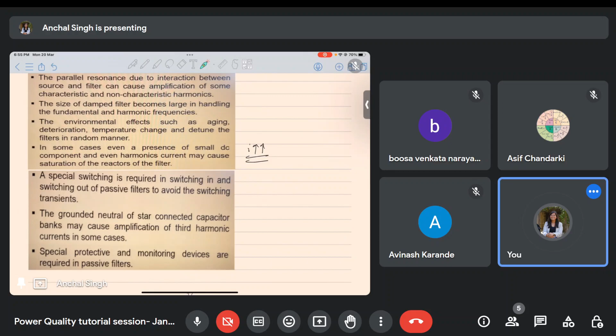Special switching is required in switching in and switching out of passive filters to avoid switching transients. So while connecting, switching transients are equivalent to connecting or disconnecting a load, right? So when I am doing that, I'll have to take special care at what point of my voltage curve I am connecting. I'll try to make the connection at the point when the voltage is very low in order to avoid the switching transients. Then if there is a ground wire present, if three-phase four-wire circuits are present, then there will be a grounded neutral. And because of the presence of that grounded neutral, there might be amplification of the third harmonic current in some cases. And then in certain cases, in order to monitor the current through the passive filters, you might need special protection or monitoring equipment as well. So it's additional cost in that case.